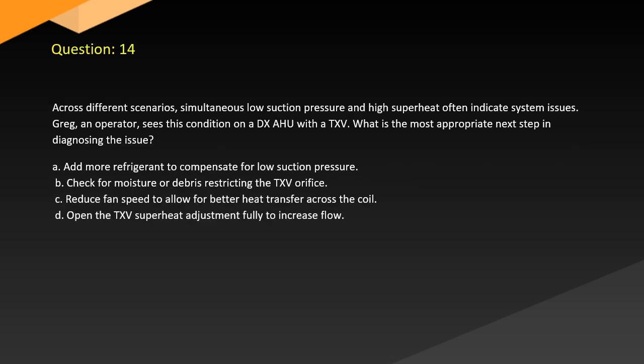Question 14. Across different scenarios, simultaneous low suction pressure and high superheat often indicate system issues. Greg, an operator, sees this condition on a walk-in. What is the most appropriate next step in diagnosing the issue? A. Add more refrigerant to compensate for low suction pressure. B. Check for moisture or debris restricting the TXV orifice. C. Reduce fan speed to allow for better heat transfer across the coil. D. Open the TXV superheat adjustment fully to increase flow.